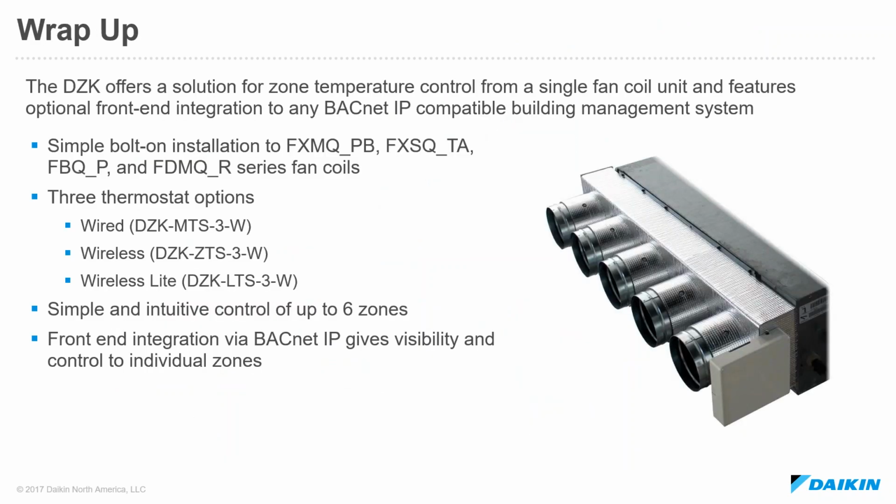So just to wrap up, the idea behind the DZK is to offer this, I typically call it a budget-conscious solution for giving individual zone temperature control from a single fan coil unit. We have that optional BACnet IP integration card to really give us some good flexibility for controlling these individual outlets from a centralized location. But the DZK is a bolt-on accessory that's compatible with the FXMQ and now the FXSQ, the FDMQ, and the FBQ fan coils. And there are 3 different thermostat options we looked at.